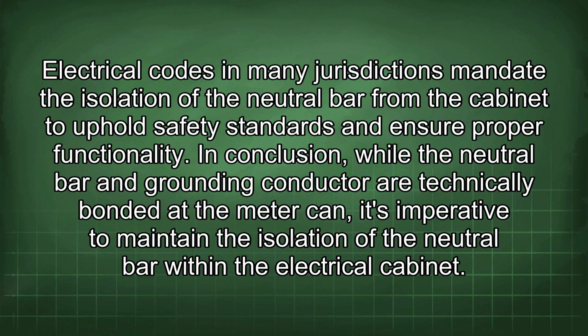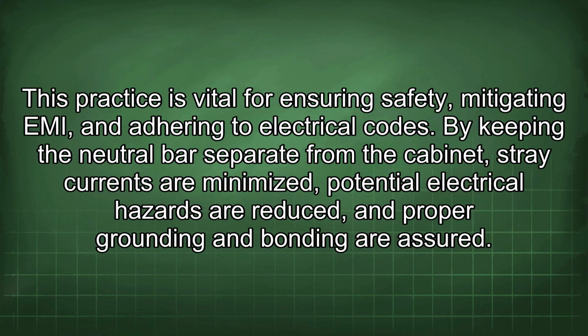imperative to maintain the isolation of the neutral bar within the electrical cabinet. This practice is vital for ensuring safety, mitigating EMI, and adhering to electrical codes. By keeping the neutral bar separate from the cabinet, stray currents are minimized, potential electrical hazards are reduced, and proper grounding and bonding are assured.